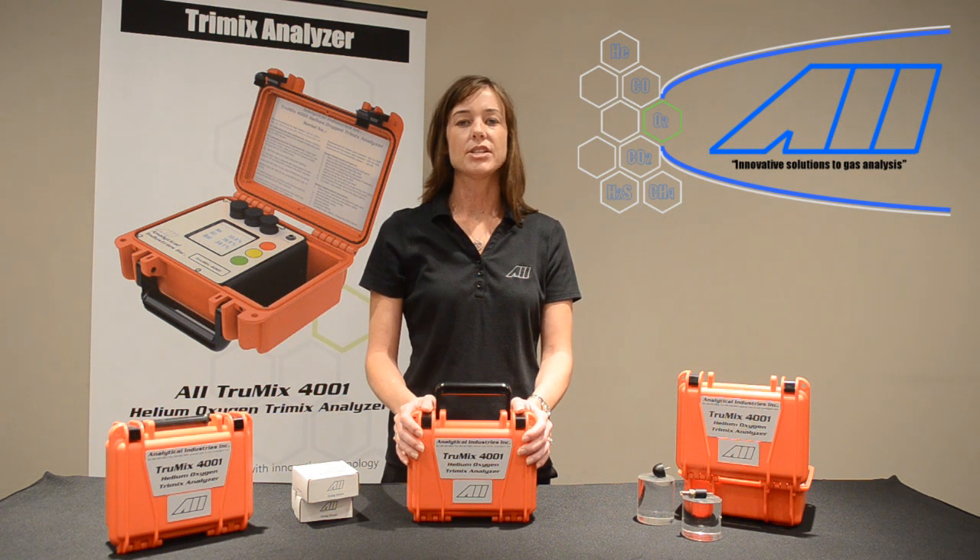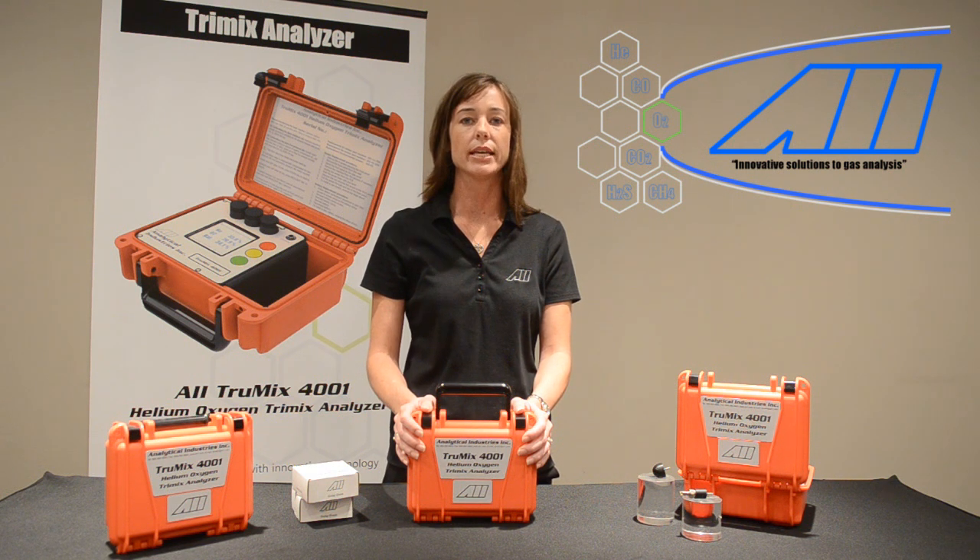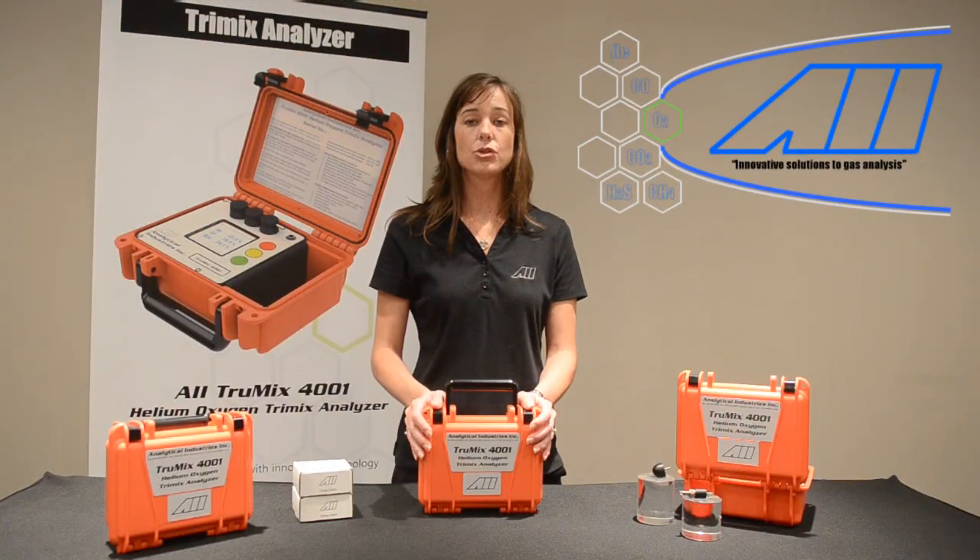The AII 4001 TrueMix Dive Gas Mix Analyzer uses a proprietary algorithm to accurately measure a combination of gases including helium, oxygen, and nitrogen. Utilizing the oxygen sensor to compensate for the helium sensor, the TruMix can accurately measure pure helium, oxygen, and nitrogen, in addition to nitrox, heliox, and trimix gas mixes in any ratio.